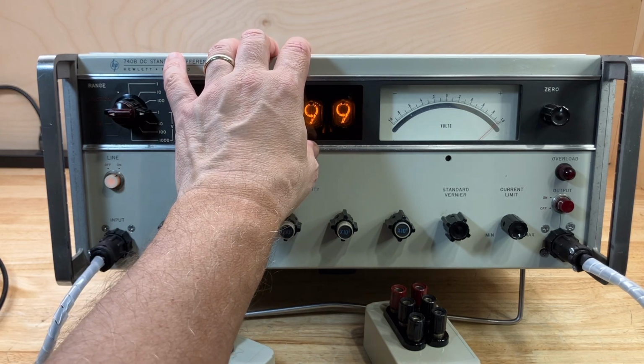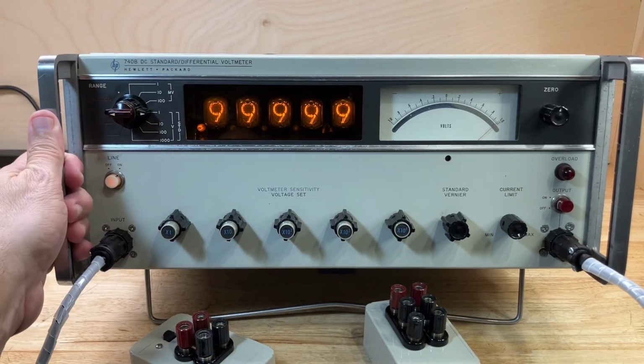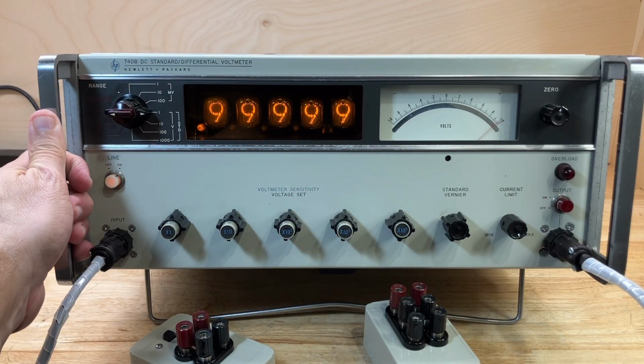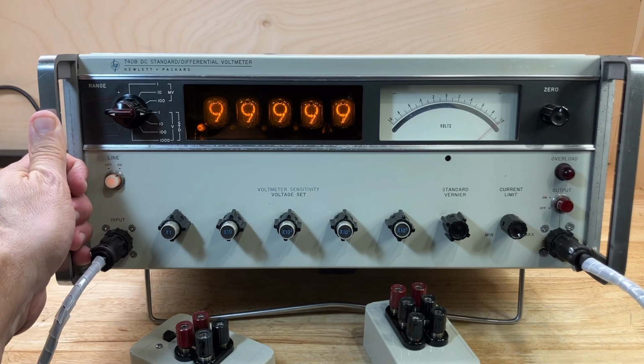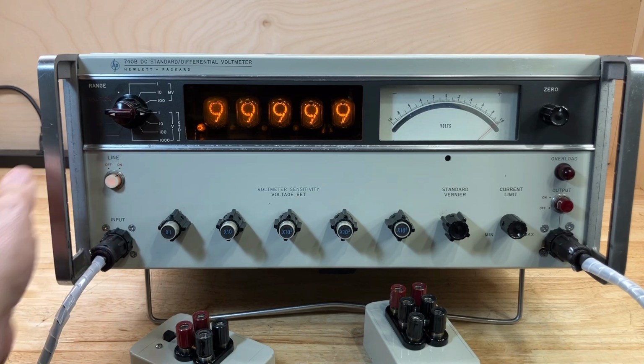Internal to this instrument, there are also two photochopper assemblies, like we've seen before on some of the other HP instruments I work with. They're very similar. There are two of them because there are two different high gain loops internal to the instrument, high gain amplifiers that need photochoppers to convert the DC voltage into an AC voltage and then back to DC again.